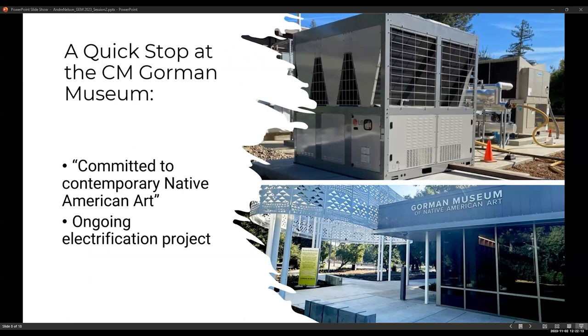The air handler and terminal equipment in these buildings was updated a few years ago. At the time, we really did want to electrify the entire building, but it wasn't feasible for budgetary reasons. Knowing that we did want to electrify it, we opted to replace the equipment's coils, which were designed for 180 degree Fahrenheit flow, with coils designed for 120 degree flow.